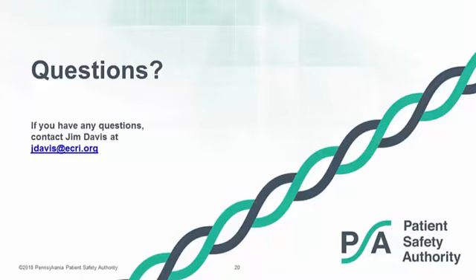And we do have one more question, Jim. Would it be a good idea to soak instruments in sterile water during longer cases to help reduce the bioburden before the enzymatic cleaner can be used, as long as the instruments can be soaked in sterile water? If it's okay with the manufacturers, I know folks that are doing that. I'm glad you're saying sterile water, because you want to stay away from the salines or anything that might be caustic and ruin the surface.